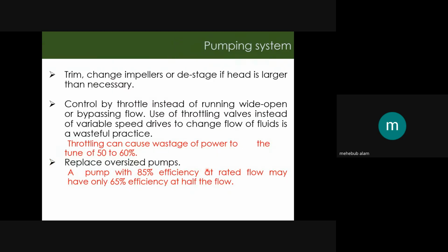For the pumping system in industry, during the design phase, the manufacturer gives the pump as per the requirement of the client. But after installation of the pump, it is sometimes observed that the pumps are oversized, meaning that capacity is not required. So we have to replace that oversized pump because it will consume more power than the requirement. Similarly, throttling can also cause wastage of power to the tune of 50 to 60%.